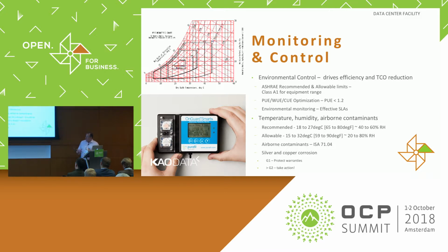So we've put in a series of monitors, and I think we're probably the first wholesale company to do that. Purafil have been working with us, and effectively we monitor predominantly chlorides and sulfides in the atmosphere, making sure we always deliver a G1 atmosphere. Within the standard there are 4 classifications: G1, G2, G3 and GX. GX means you will have a failure of your electronic equipment because either the solder or the circuit boards themselves will corrode. So it's very important that this comes into the monitoring aspect of the data center.